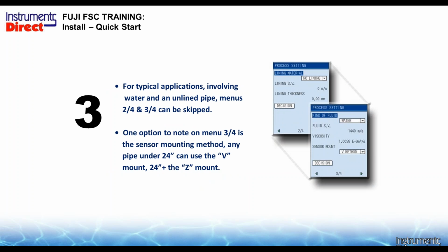For typical applications using water and unlined pipe, you can skip a lot of this information here. But say you had a cast iron pipe with a mortar lining. There's really two choices: a single lining and a dual lining. It's usually 0.125 is the traditional wall thickness for a mortar lining application there. We do not like exterior mortar linings with rebar under it. Not good, not a good application for any ultrasonic flow meter there.